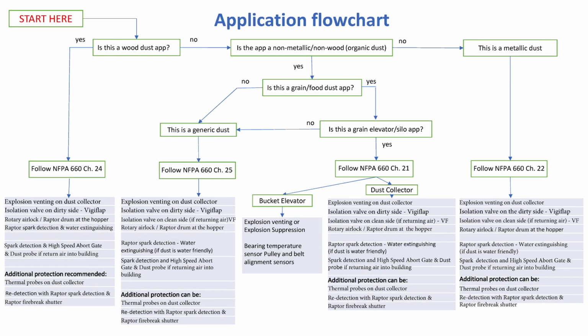So when we talk about different types of protection and different types of safety equipment for combustible dust applications, we use what is referred to as the NFPA, which is the National Fire Protection Association. And in that code, in that standard, it talks about different commodities. With the new NFPA 660, it's combined all the different commodities into different chapters. So depending on the type of dust you have, depending on what chapter you follow. So for example, if it's a wood dust application, you would still use NFPA 660, chapter 24, and it points out all the risks and it points out all the different types of equipment that you would need in association with either fire protection or explosion protection. Next slide, Andy.